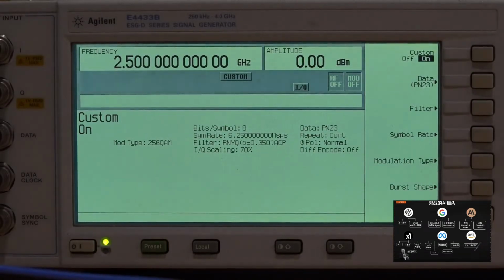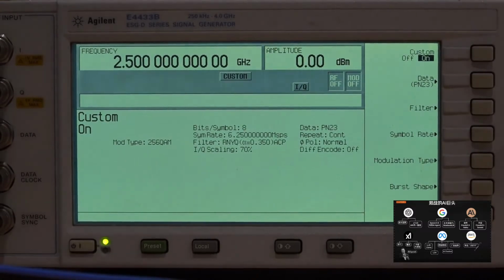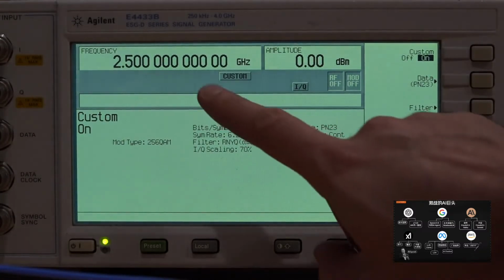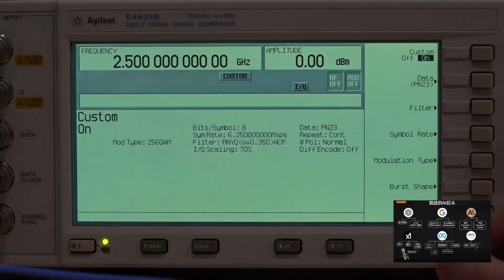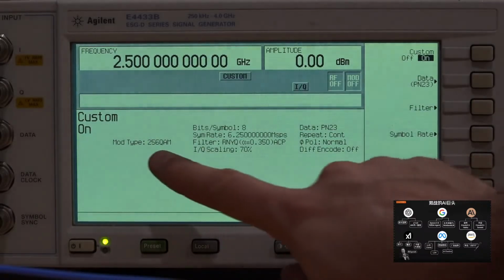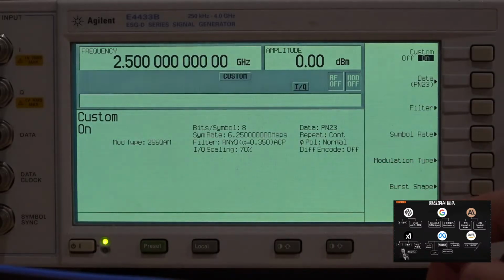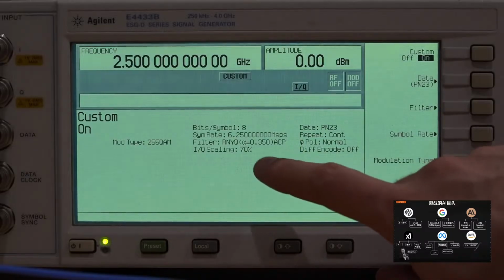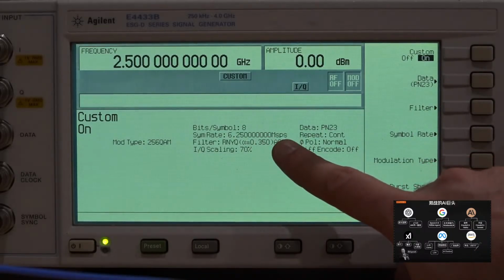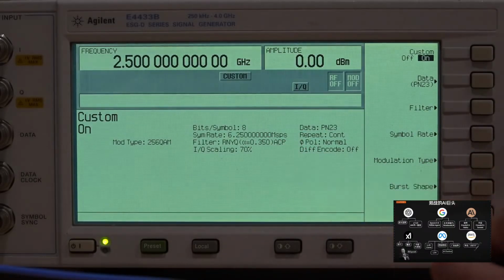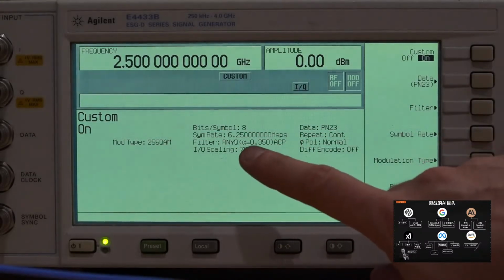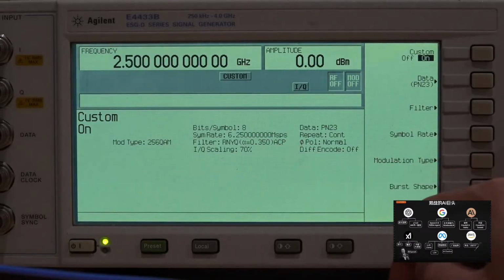So the calibration ran just fine. Let's go ahead and analyze a modulation with this instrument. I have a carrier set to 2.5 gigahertz, amplitude is 0 dBm. We're going to take a look at a 256 QAM modulation, single carrier. That's 8 bits per symbol, of course, at a symbol rate of 6.25 megasymbols per second. That's the highest this instrument can do at this modulation rate. So that's still quite a bit of data coming out of this. And then we're going to do a filtering of 0.35 root raised cosine.